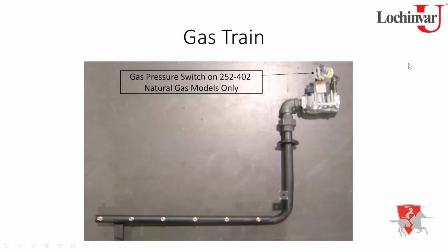Don't we all? All right, so let's get into the gas train. Now we talked about the burners. Now we got to see what's feeding the burners, right? And that's our gas train. So up top, you've got a single combination dual seat gas valve. So it's your combination valve regulator. You've got your individual orifices going down through your manifold. The difference between natural gas and propane is going to be the orifices, obviously, the size of the holes in the orifice, as well as the gas valve, which would be a different gas valve.